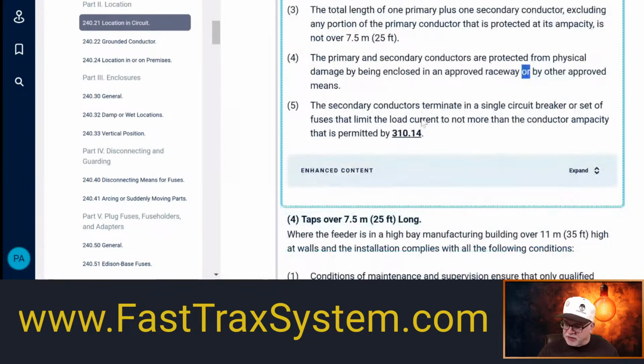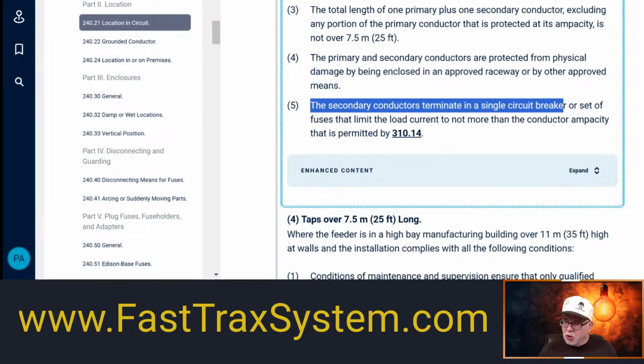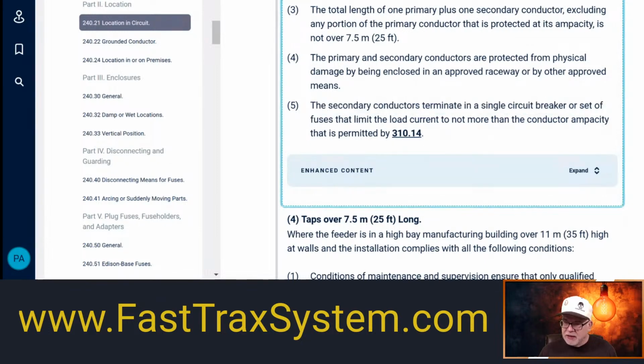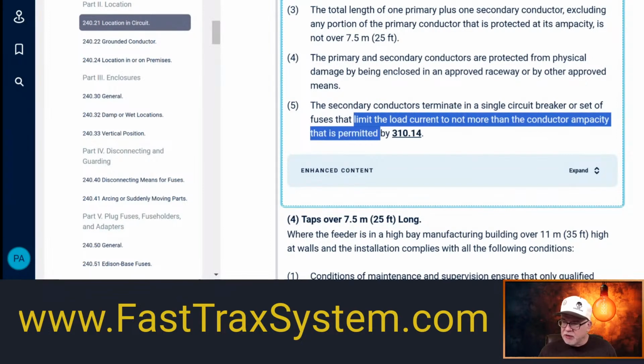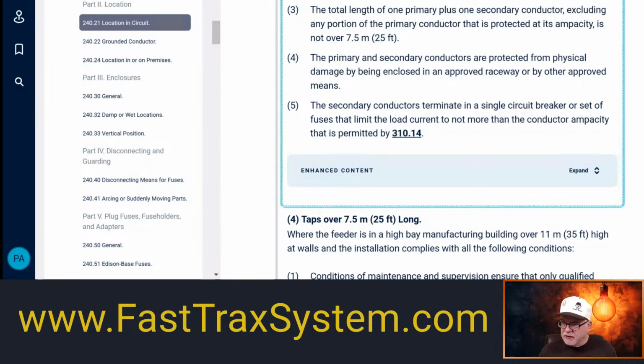All right, last caveat. Okay, we're almost there, folks. We're a little over the hour, but we're almost there. Hang with me. Last caveat is the secondary conductors terminate in a single circuit breaker or set of fuses that limit, you hear me? That limit the load current to not more than the conductor's ampacity that is permitted in 310.14, okay?